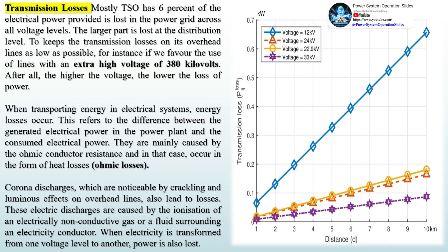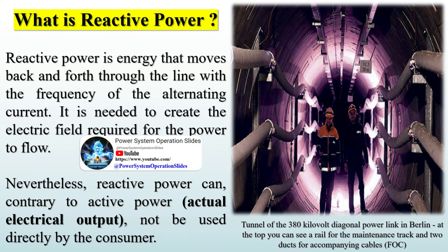Transmission losses: most TSOs worldwide see around 6% of the electrical power provided lost in the power grid across all voltage levels, with the larger part lost at the distribution level. To keep transmission losses as low as possible, operators favor the use of lines with an extra-high voltage of 380 kV. After all, the higher the voltage, the lower the loss of power. When transporting energy in electrical systems, energy losses occur — this refers to the difference between the generated electrical power in the power plant and the consumed electrical power. They are mainly caused by ohmic conductor resistance, occurring in the form of heat losses. Reactive power is energy that moves back and forth through the line with the frequency of the alternating current; it is needed to create the electric field required for power to flow, but contrary to active power, cannot be used directly by the consumer.